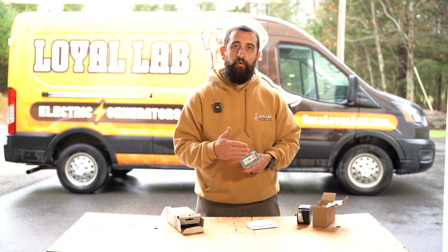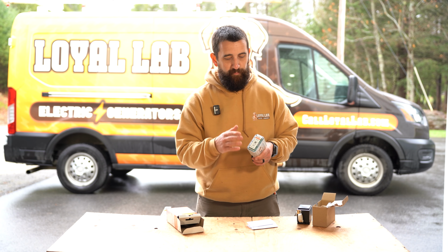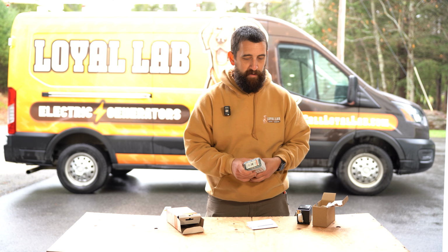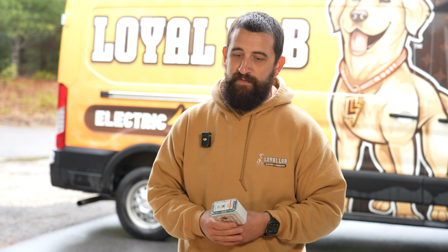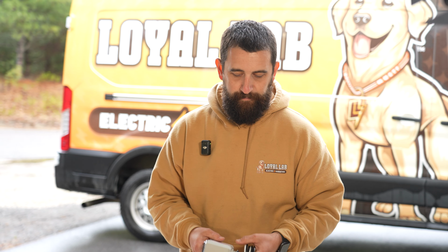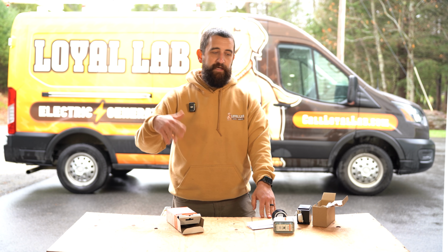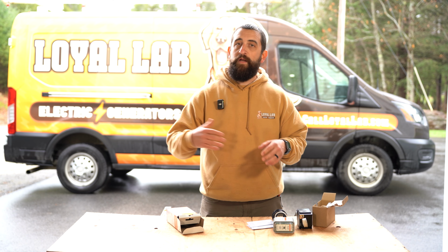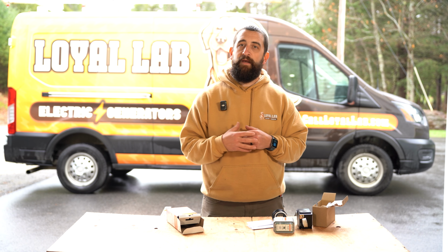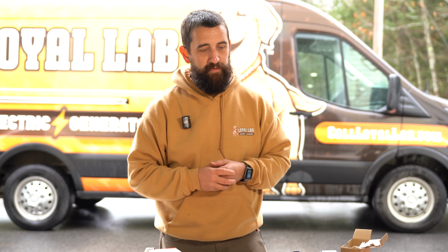So it's really important to periodically go to your electrical panel and take a look at it to see if the light's on, or when we do our annual inspections for our members, we can take a look at that for you as well. Surge protectors, without getting too technical, are monitoring the voltage coming in, and if they see something out of the realm of what's considered normal, they can distribute that through the grounding system like they're supposed to.